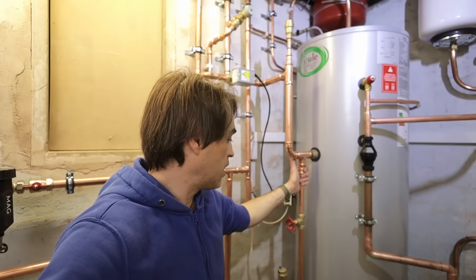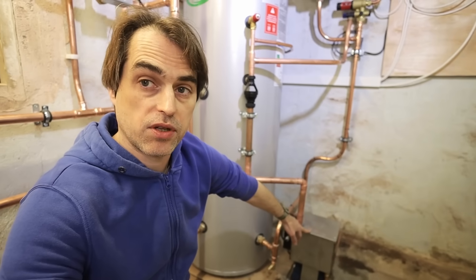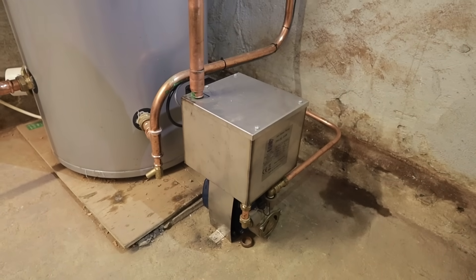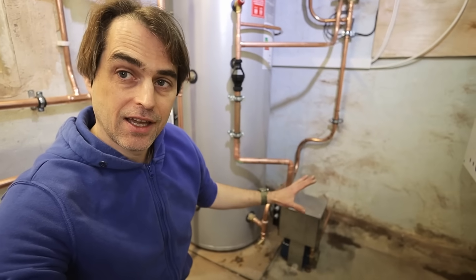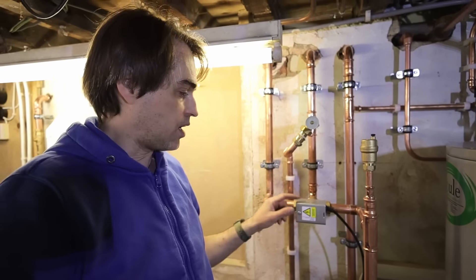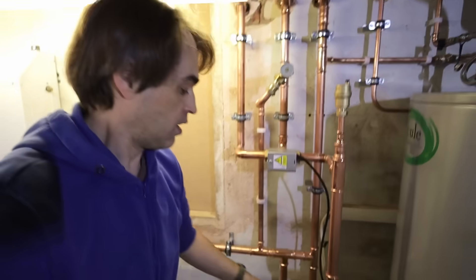Here we've got a new dual unvented cylinder - a high gain cylinder - with a coil of almost three square metres. We've got a new balanced cold going to the property, new cold supply, new mains supply in 22 millimetre copper. This is an interesting item - a high temperature pump to pump away our system pressure relief and cylinder temperature and pressure relief. It's the only pump I'm aware of that can continuously pump water close to 100 degrees C. It's quite expensive at about £700, but I'm not aware of any cheaper equivalent, so if you know of one, comment below.